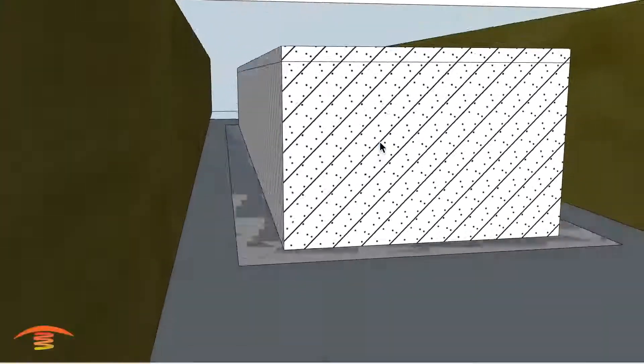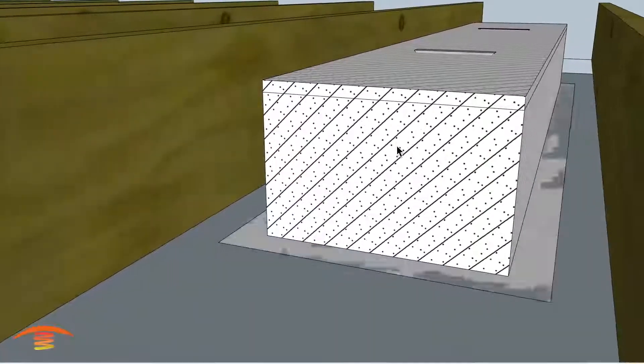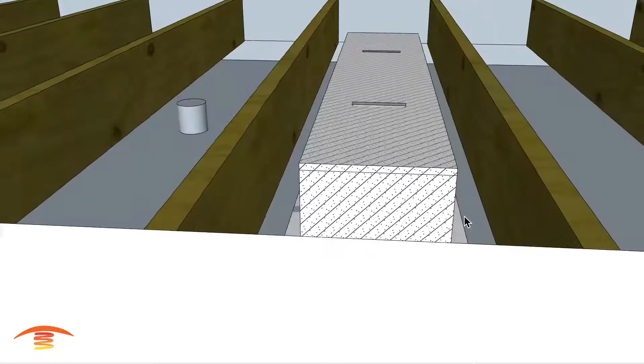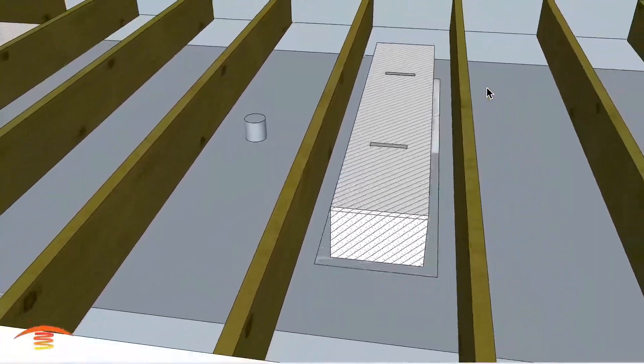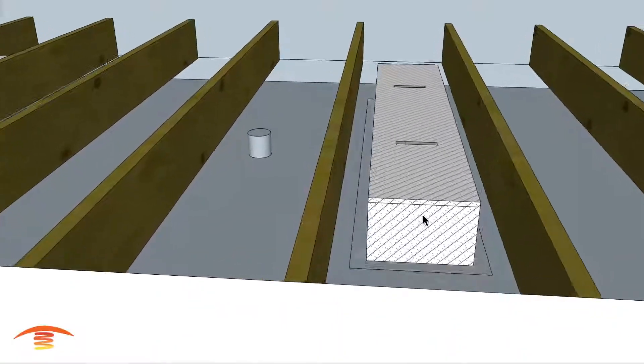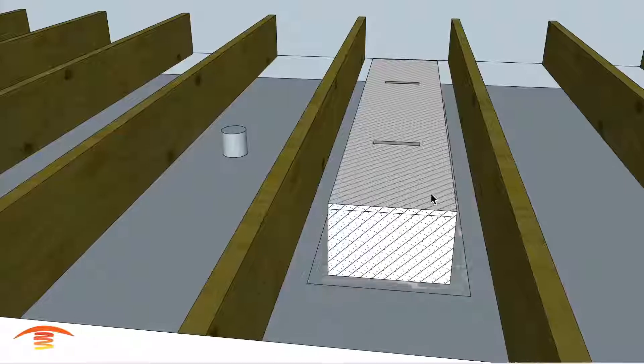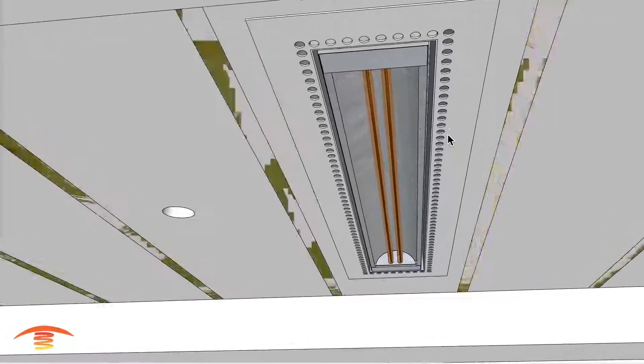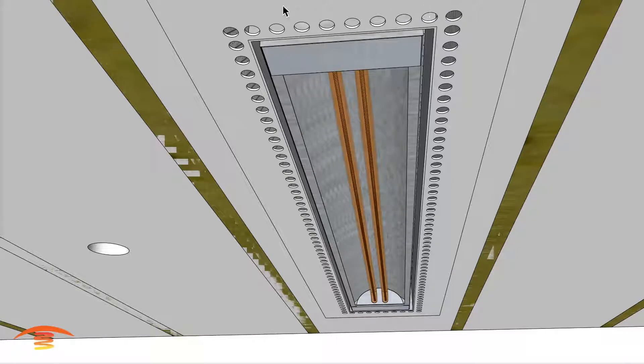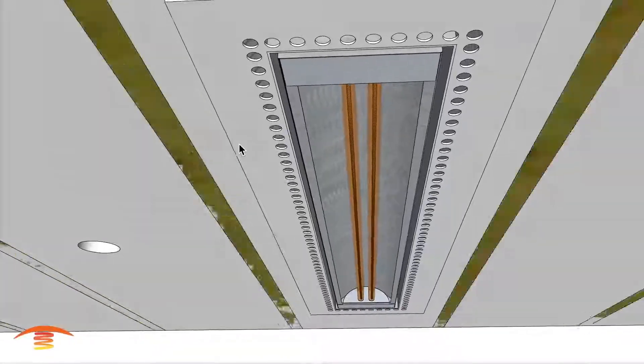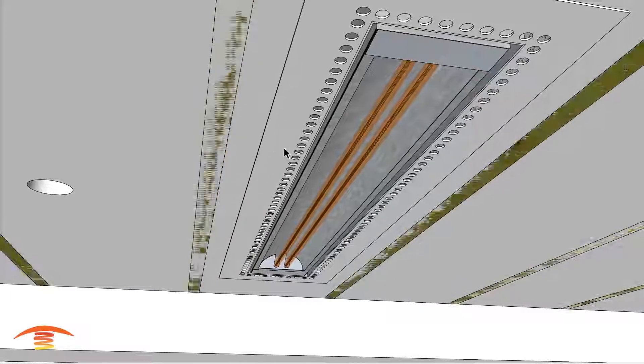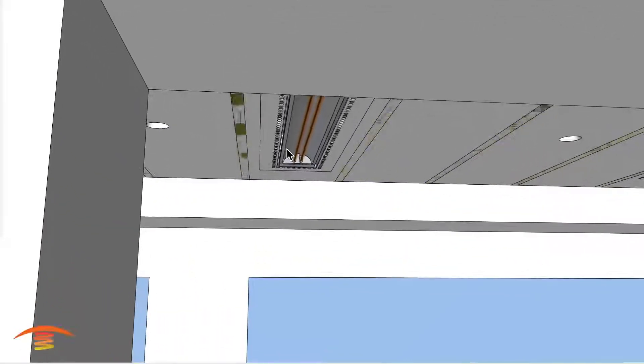Here's the heater and this is the flush mount frame. And then the contractor installer would put in a 7/8ths drywall one hour rated drywall finish into the space. So what you might do is block this area, at least block it from here to here, here to here, and then install your one hour fire rated drywall finish. And that needs to be on all five sides. So left, front, back, left, right, and top. And then the bottom would be obviously hollow. Now you can finish this all the way up to one half inch away from these holes around the whole side. So it could be a stucco finish all the way up, or you can just place it like I have here, which is finished on the surface. I like the other option better. It just looks a little bit nicer.